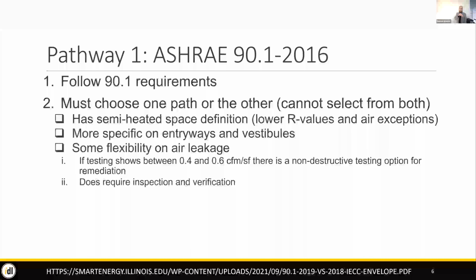With 90.1, if you do testing, there's a little bit of a grace period. With 2018 IECC, if you just test for air tightness and it comes back higher than 0.4 CFM per square foot of the envelope, you just fail. You're going to have to get it retested and make sure it absolutely passes.